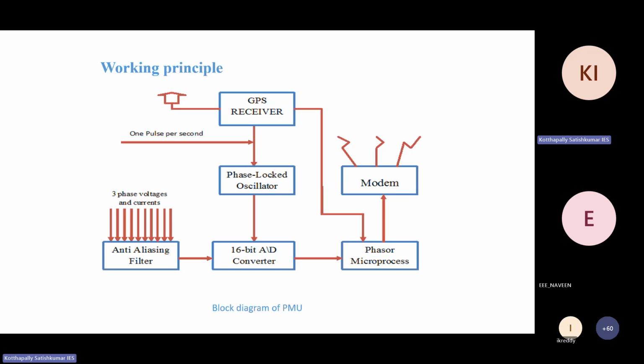So this is the working principle of PMU, how exactly a PMU works in a substation. For example, you place a PMU in the substation. What are the inputs to this PMU? Three-phase voltages and three-phase currents are the inputs to the PMU. You will give these three-phase voltages and currents to the PMU, and you will get output in the modem. The output of this microprocessor is the phasors, the positive sequence components of the voltage and currents. From that, you can calculate anything else. Here we give three-phase voltages and currents to this anti-aliasing filter, which is nothing but a low-pass filter.